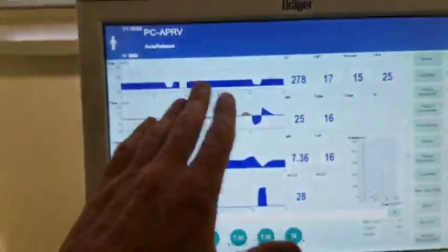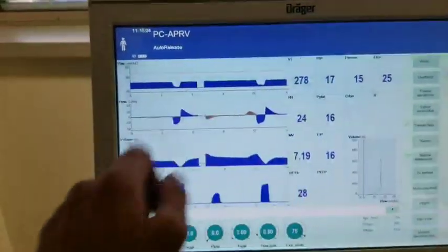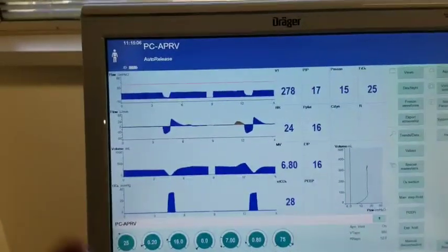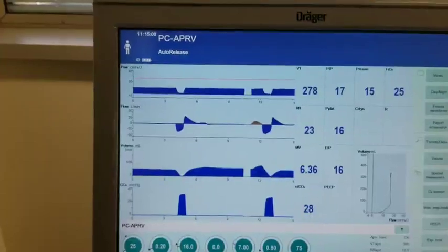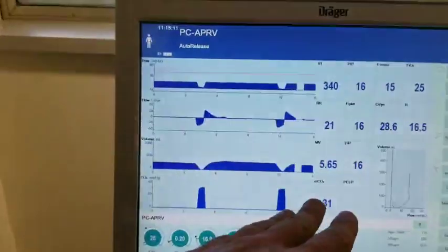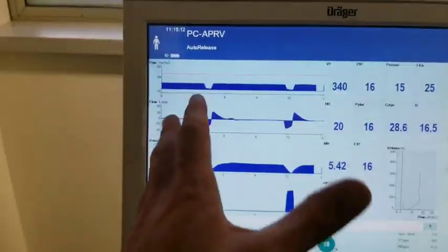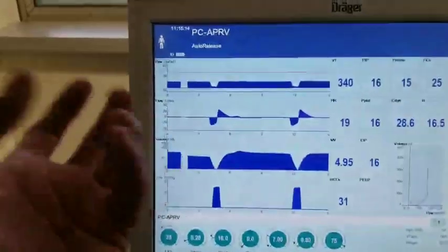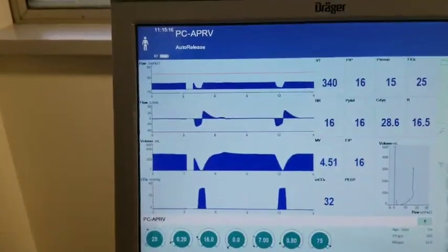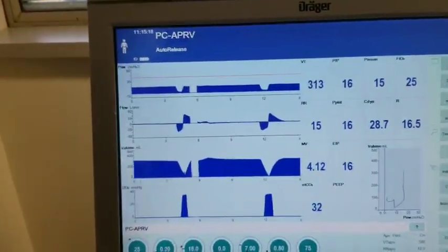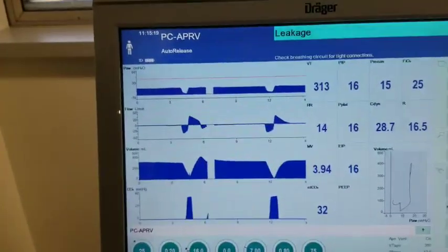We're not giving the diaphragm a vacation. We lose function very rapidly, especially in controlled modes. So the variation in the respiratory tidal volume rate is more physiologically normal. There's a variation and the patient can breathe all throughout the cycle.